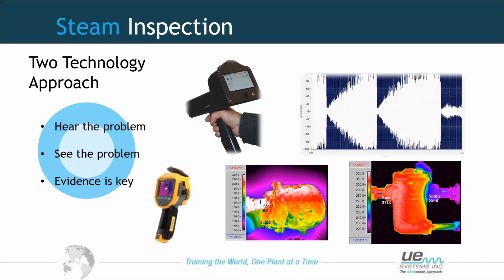But that doesn't tell me that the trap is not working correctly, because it could be the fact that the trap is blocked. So this is where using ultrasound will also help us with understanding the condition. And if we have the ability to do a sound recording, then we can see on spectral analysis the sound increasing and decreasing. Again, evidence is key when you need to justify if you want to do something on site.